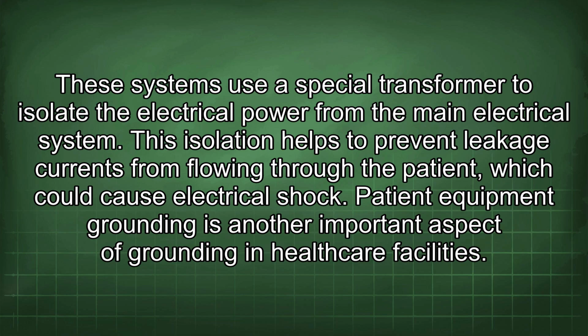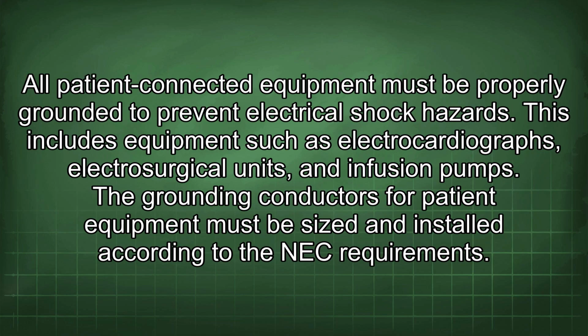Patient equipment grounding is another important aspect of grounding in healthcare facilities. All patient-connected equipment must be properly grounded to prevent electrical shock hazards. This includes equipment such as electrocardiographs, electrosurgical units, and infusion pumps. The grounding conductors for patient equipment must be sized and installed according to the NEC requirements.